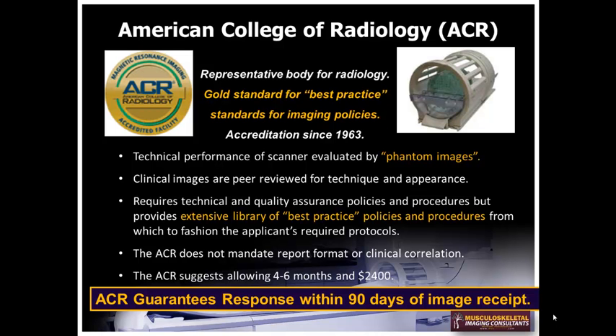The American College of Radiology, or ACR, is the representative body for radiology. It maintains the gold standard for best practice standards for imaging policies and has been an accrediting facility since 1963. The ACR process for accreditation includes an evaluation of the technical performance of the MRI scanner by submission of phantom images. We'll talk about this in a minute. The application also requires submission of clinical images that are peer-reviewed to evaluate for technique and image appearance. The application requires technical and quality assurance policies and procedures, but the ACR does provide an extensive library of best practice policies and procedures from which you can fashion your site's protocols.